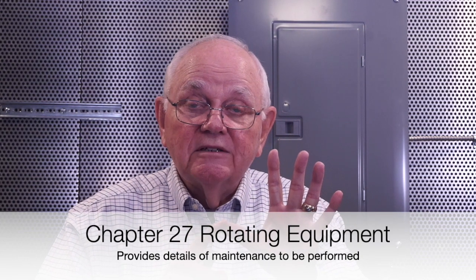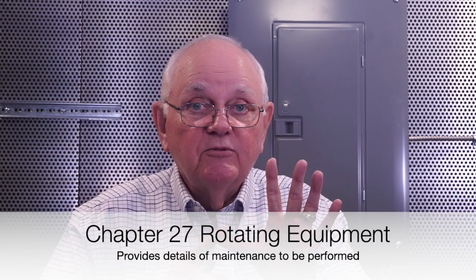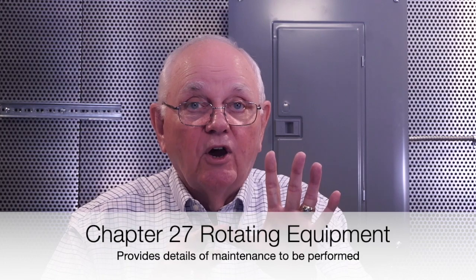How often do I do it? Well, it depends. If I have a predictive maintenance system I'm using, use that. If I don't, Chapter 27 on rotating equipment tells me, for instance, I do my electrical testing. If it's in condition 1, meaning it's basically new equipment, I only do my electrical testing every 5 years. The worst case scenario would be condition 3, where that motor's getting older, it's been in service for quite a bit of time, or maybe we've watched some of the values start to decrease on our tests over time. So that drops it to condition 3, and now instead of every 5 years, I do my maintenance testing every year.